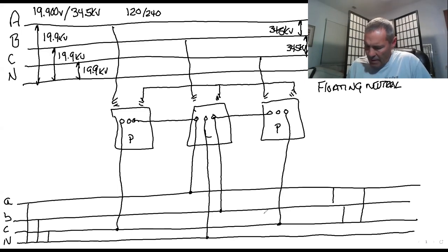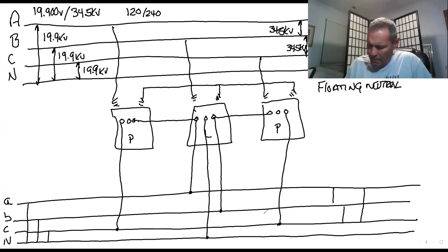A little bit different from the other one, right? Yeah. It is. On the other one before, what we had in the lighting transformer is that went to B on the left-hand side, then C on the right-hand side of lighting, then both power transformers were connected to A. This works fine also, what I've got drawn right here. And it stays in line with my open delta. If I took my hand and covered up the left-hand side transformer, I'd have an open delta bank perfectly. Now I've just added this transformer on the left-hand side and connected it with C also because I need more three-phase power.